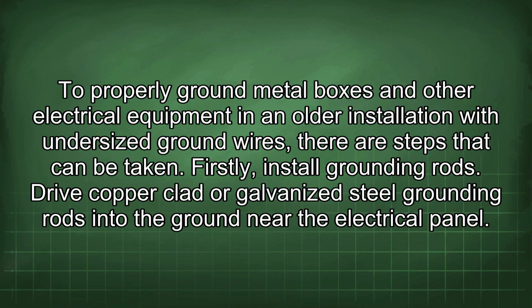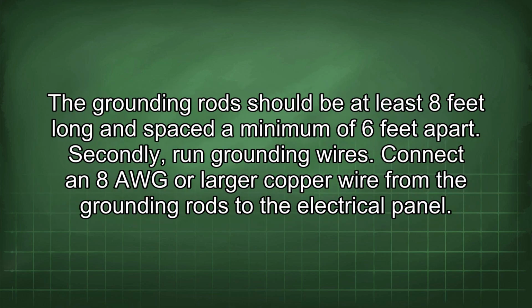To properly ground metal boxes and other electrical equipment in an older installation with undersized ground wires, there are steps that can be taken. Firstly, install grounding rods. Drive copper-clad or galvanized steel grounding rods into the ground near the electrical panel. The grounding rod should be at least 8 feet long and spaced a minimum of 6 feet apart. Secondly, run grounding wires. Connect an 8 AWG or larger copper wire from the grounding rods to the electrical panel.